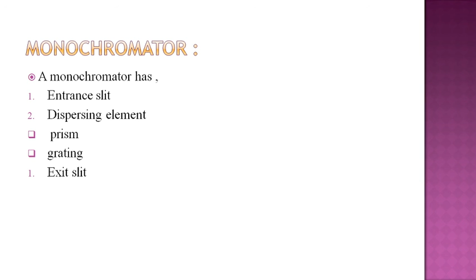Filter has 2 types. First one is absorption filter and second is interference filter. Now see here monochromator. Monochromator has entrance slit, dispersing element, that is prism and grating, and then there is an exit slit. The use of prism is that when light passes through a prism, it gets separated into different colors. And grating consists of a large number of parallel lines ruled on a highly polished surface of aluminum. Then there is an exit slit. These are the parts of monochromator.